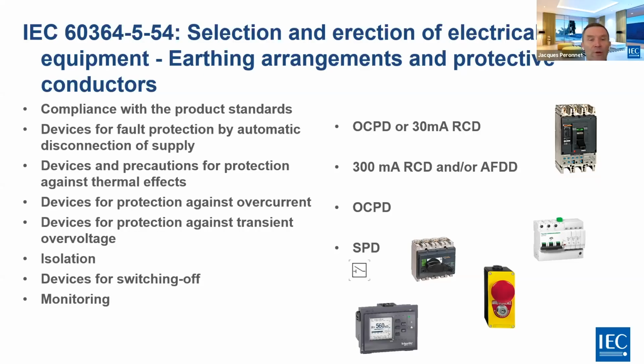So in the selection of equipment, you are going to have the correct selection of the device. So this is the part 53 and not 54, as mentioned in the slide. Sorry for the mistake. So this is where we are going to ask that the product you are going to select is compliant to an IEC standard in order to make sure that the behavior of this device is known and tested. So this is where you are going to select the device for fault protection by automatic disconnection of the supply. So it's OCPD or 30 milliamp RCDs.